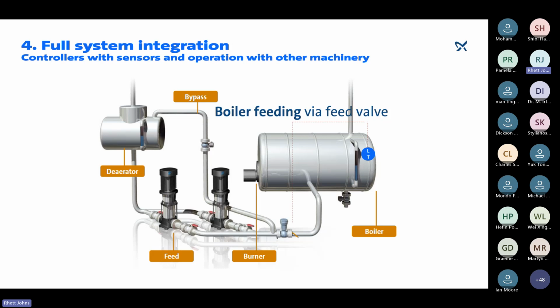This, however, requires that the feed pump is set to continuous operation. So the pumps are running continuously, regardless of the demands on the steam needs for the boiler. The benefit of a system like this is that the boiler feed water flow is adjusted according to the steam consumption, and it's also a tried and tested method of boiler feed control. The drawbacks are that you need to use a bypass in order to take off the excessive flow going through these pumps, and the feed valve maintenance and replacement is incredibly expensive in a system like this, and they fail regularly. We're talking about multiple times a year if you are really using that feed valve frequently.